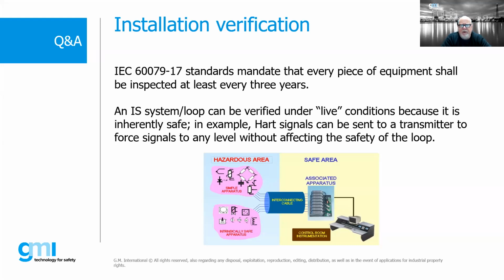An IS system can be verified under live conditions because it is inherently safe, right? But we want to be careful if we're testing, for example, IS barriers to see if they're actually working. We don't want to introduce electrical charges into an IS loop in a hazardous area. So we want to disconnect the leads from an IS barrier. There are different methods to treat IS, so we do need to be careful. Generally speaking, we want to go through our gas-free permits. We want to do our lockout, tagout. But there are some exceptions that we can do, especially around IS.